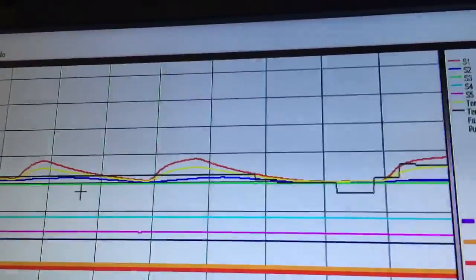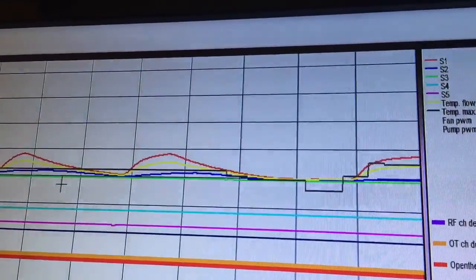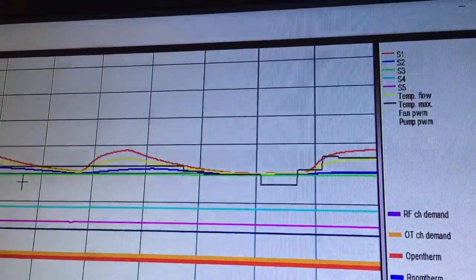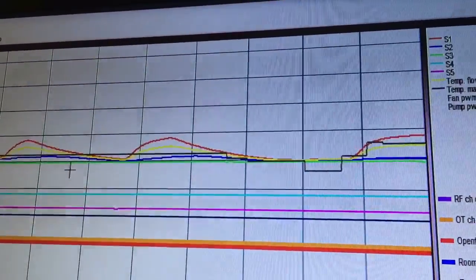Which if you relate it over to here where we were before, you can see it's actually calling for 45 degrees over there. So with the room compensation on, it calls for a bit more higher temperature than if you were just using the outside temperature compensation on its own.